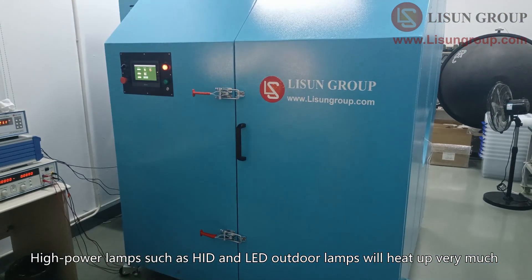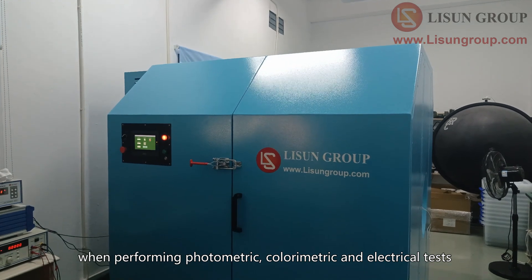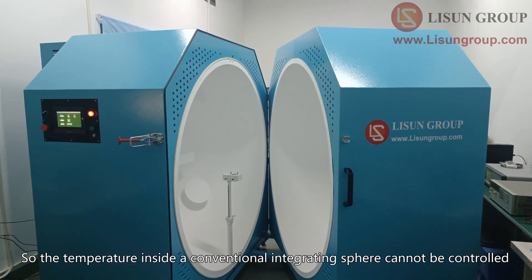High power lamps such as HID and LED outdoor lamps will heat up very much when performing photometric, colorimetric and electrical tests, so the temperature inside a conventional integrating sphere cannot be controlled.